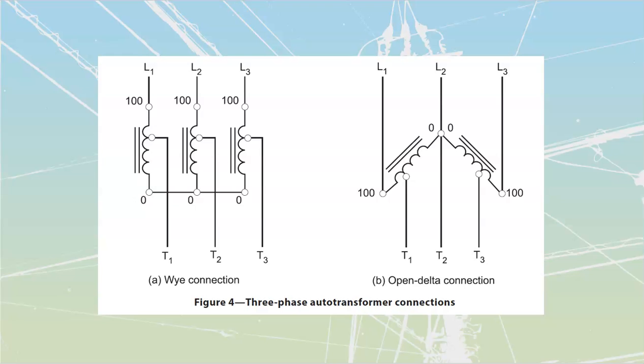There are two main connections that we can have. We can have a Y connection for these, or we can have a delta connection. And these are drawn in a bit of a different manner than you're probably used to, but you'll see that these over here are all labeled 0, that's going to be an X0, or a common point that we are going to have. And it's as if I've got a Y type of winding, and we're just tapping off partially down each of these. That's all that these T1 taps are going to be. This other one over here, the open delta, we're only going to have 2 windings, which makes an open delta starter even cheaper and easier for us to operate.